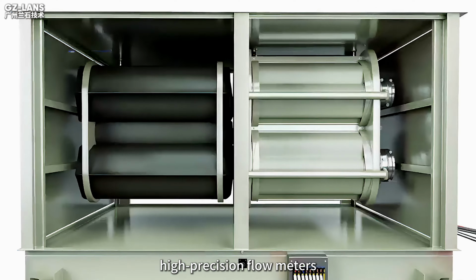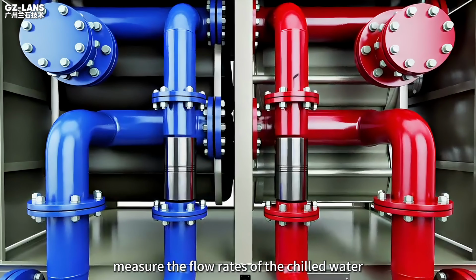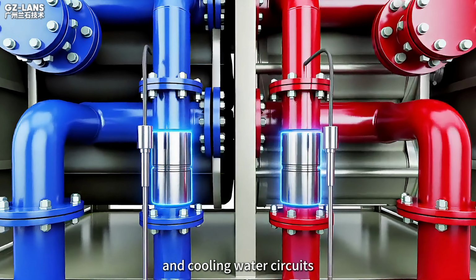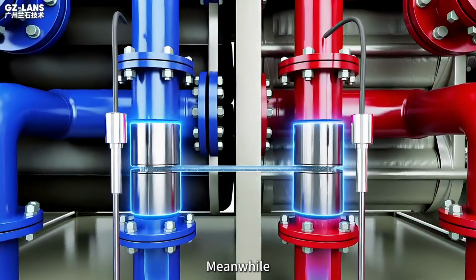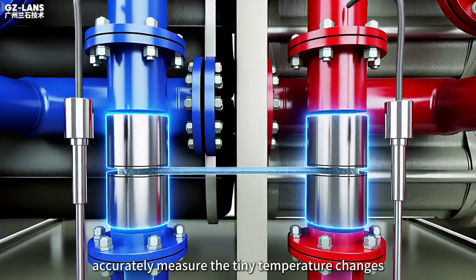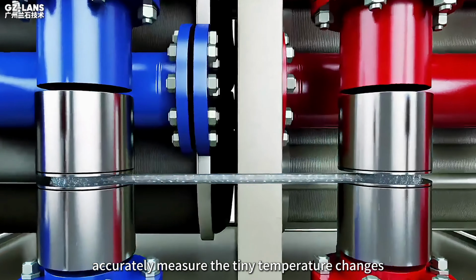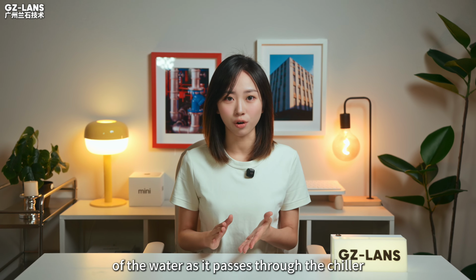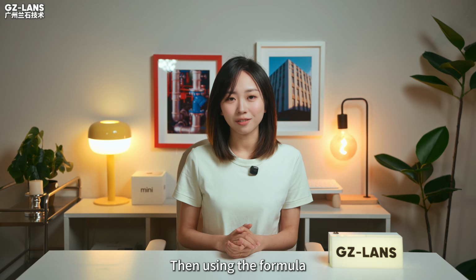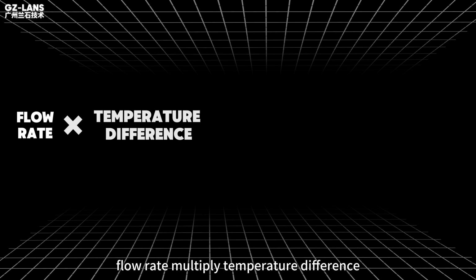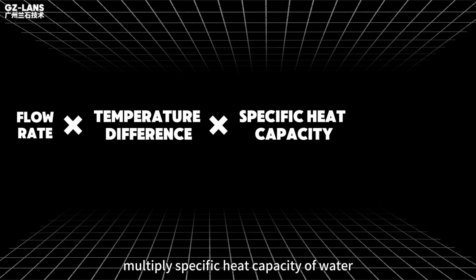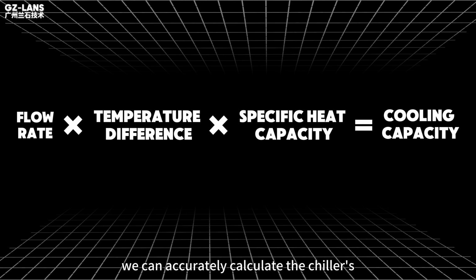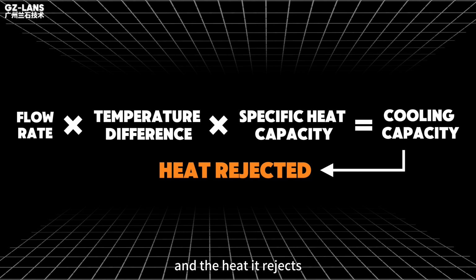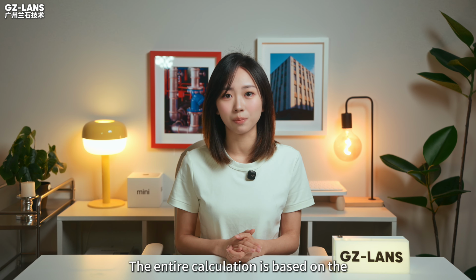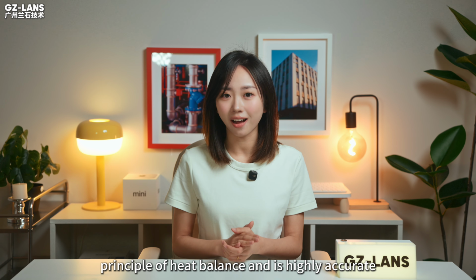Specifically in the lab, high-precision flow meters measure the flow rates of the chilled water and cooling water circuits. Meanwhile, platinum-resistance thermometers accurately measure the tiny temperature changes of the water as it passes through the chiller. Then, using the formula, flow rate multiplied by temperature difference multiplied by specific heat capacity of water, we can accurately calculate the chiller's cooling capacity and the heat it rejects. The entire calculation is based on the principle of heat balance and is highly accurate.